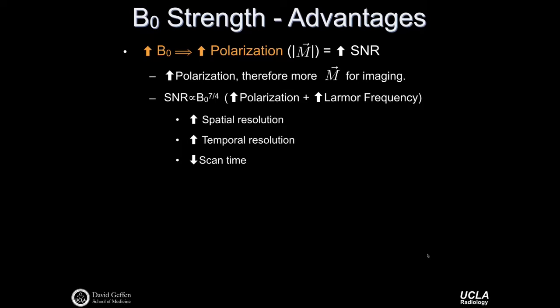There are several advantages and disadvantages to B0 field strength. Increasing B0 increases total polarization according to the Zeeman splitting equation, increasing the available bulk magnetization. The signal-to-noise ratio, a measure of image quality, is proportional to B0 to about the 7/4 power—a consequence of both increasing polarization and increasing Larmor frequencies, since higher frequencies lead to stronger detection. With higher signal-to-noise, we could increase spatial resolution, increase temporal resolution, decrease overall scan time, or various combinations of these.